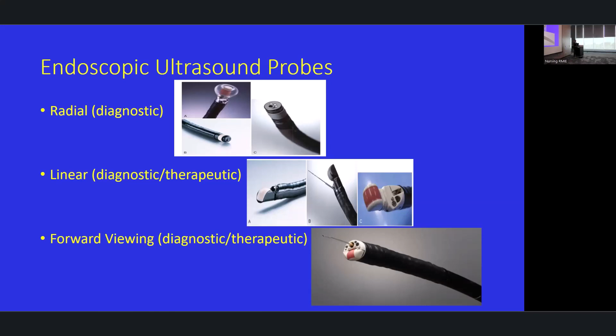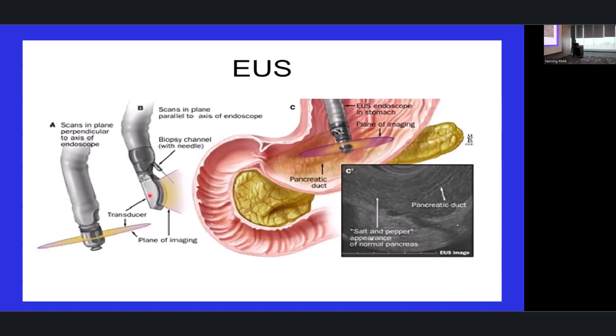So here's another take just to highlight. We have the radial probe here, the transducer, and this is the linear probe here, the transducer, and the plane of image generation is different for the two different types of scopes. So you can appreciate with the radial scope, the image generation from the sound waves is perpendicular to the probe, and it creates an image that almost looks similar to a CT scan on axial imaging. So we use the ultrasound and we get a cross-sectional image based on where the probe is located relative to the organs and areas of interest. With a linear transducer, the image is oblique, at an oblique angle in terms of the sound wave propagation, and it really requires device manipulation and orientation to get a better understanding of the anatomy that you're visualizing. So it's a little different in terms of the visual field that's generated.